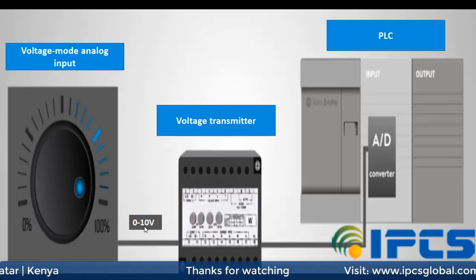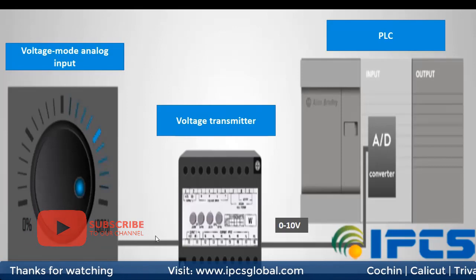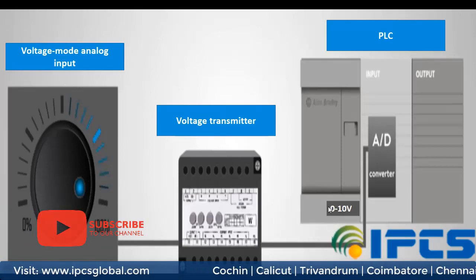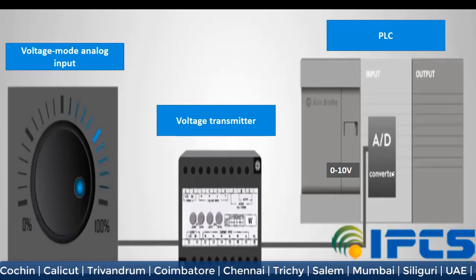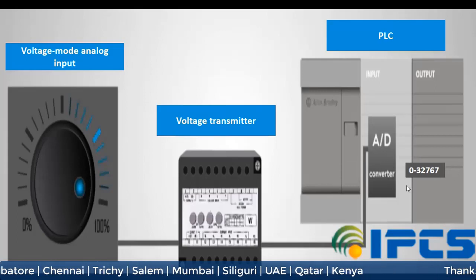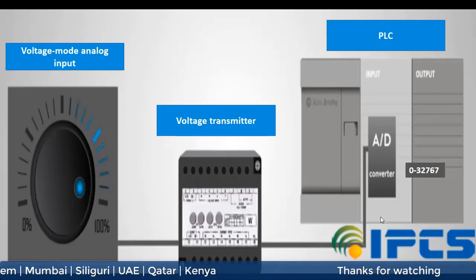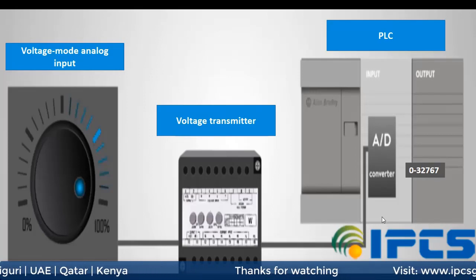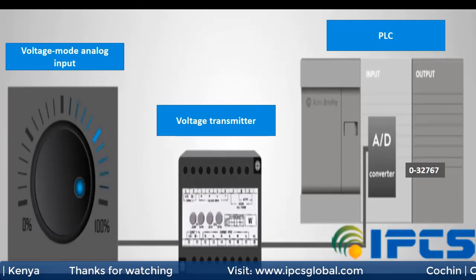Here our PLC input is 0 to 10V. When this analog input signal enters the analog PLC, it goes through an ADC and converts to a digital value. By using the SCL instruction, we can scale down the digital value to a range which will be meaningful to the operator and other users of the system.